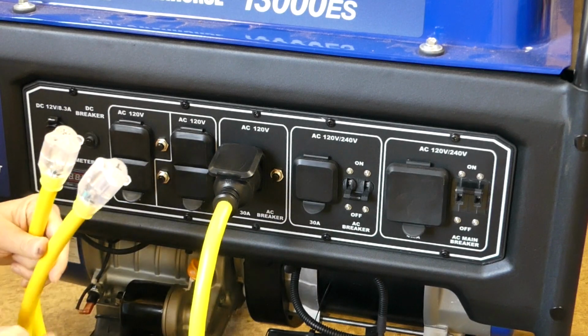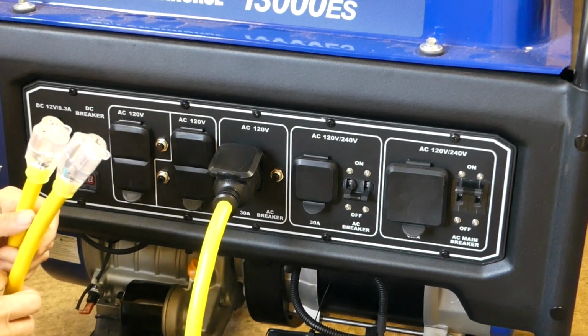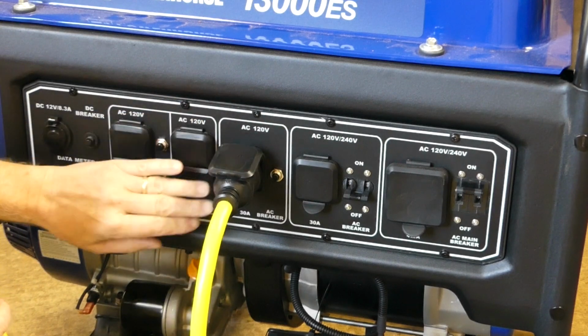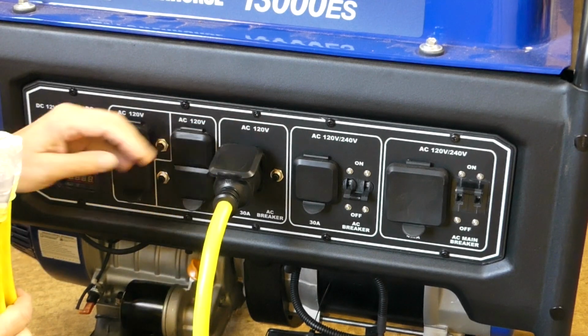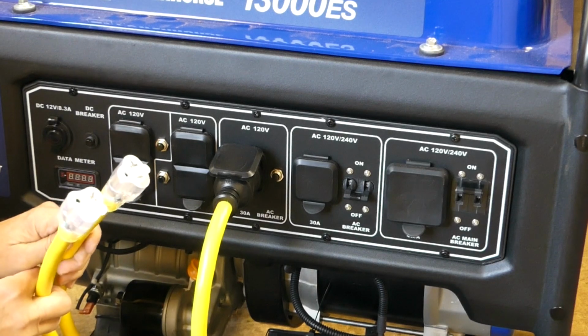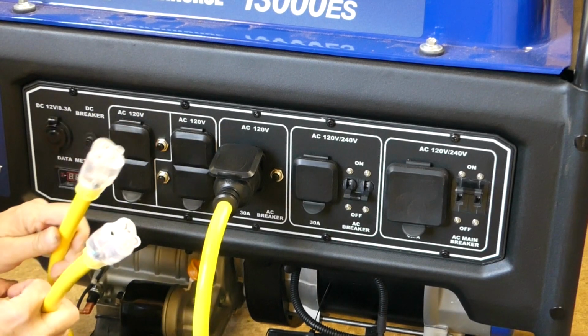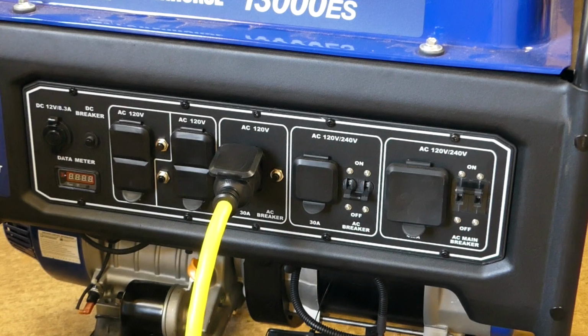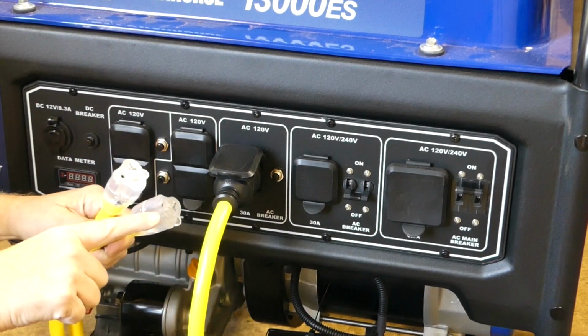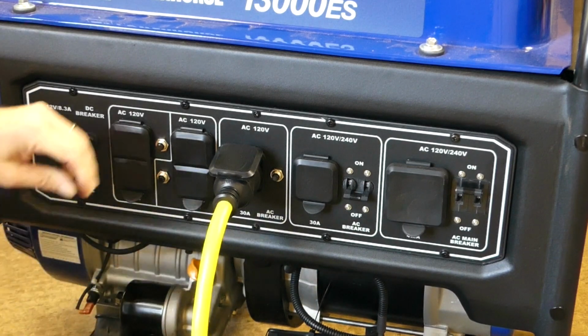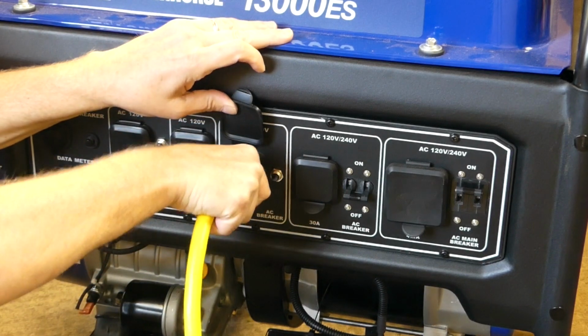As long as we can maintain the wattage below the rated output for this receptacle, for this breaker, of 3,600 watts, we can put 2 devices on here, basically 15 amps per side.